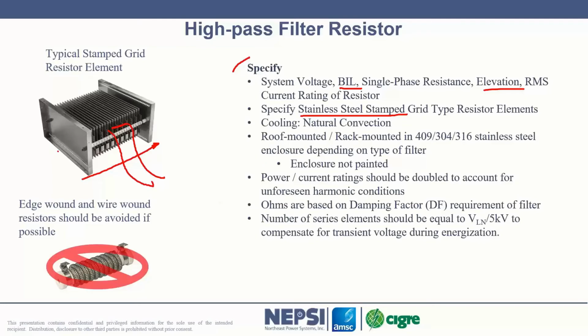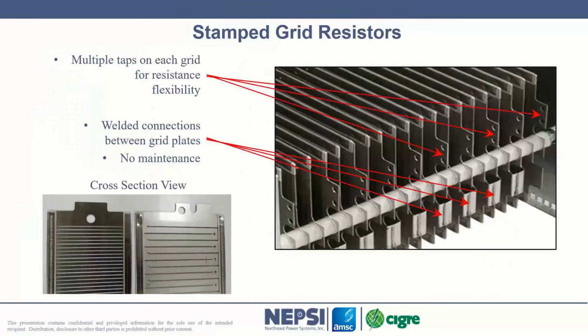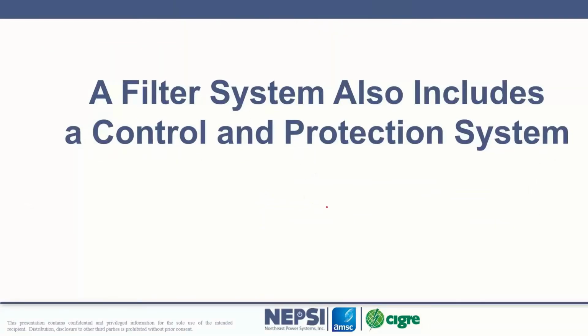There's also this rating factor thing. These typically have a 5 kV rating to them. So we typically take our line to neutral voltage and divide by 5 kV, and we would put that number of these in series. So a 33 kV system is roughly, I don't know the numbers, let's do 34.5. That's what I'm typically used to. That's equal to 19.9 kV line to neutral. We would take that 19.9 kV divided by 5 and basically put 4 of these in series. And the reason being is during switching operations, you can get a voltage strike through the resistor because of the transient voltage.